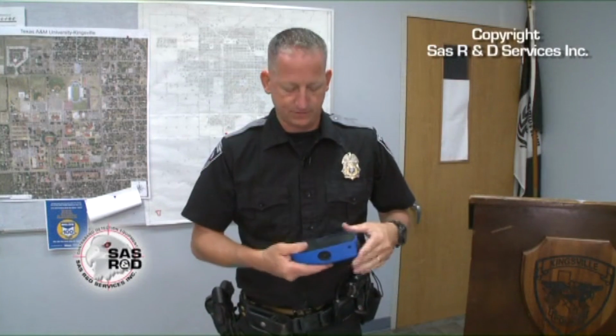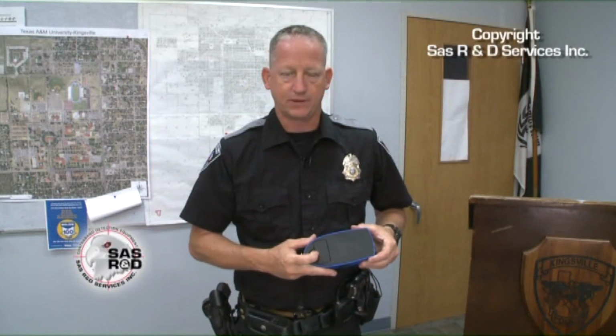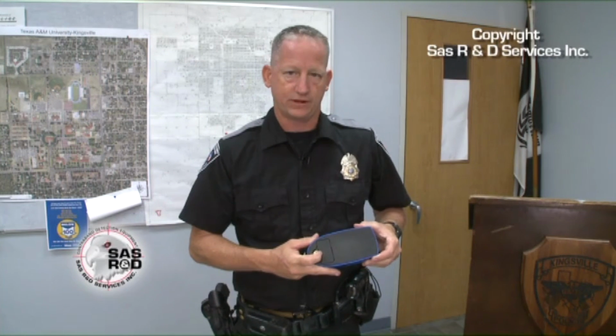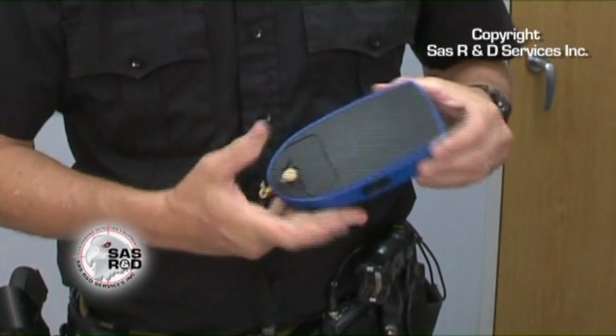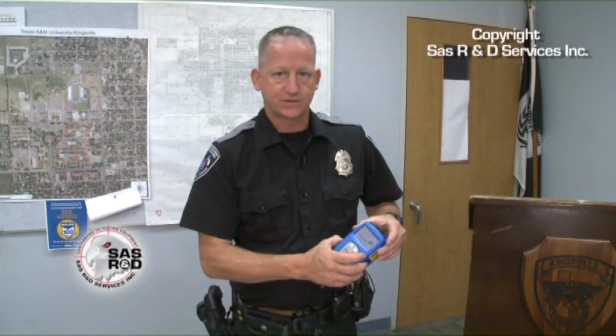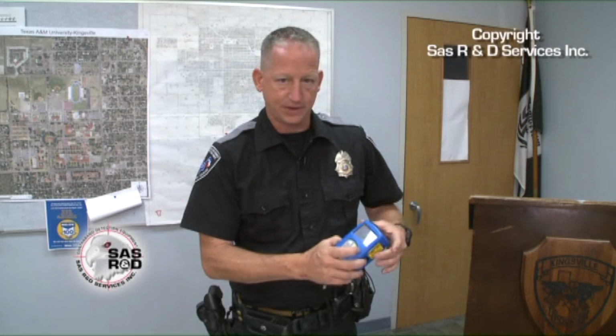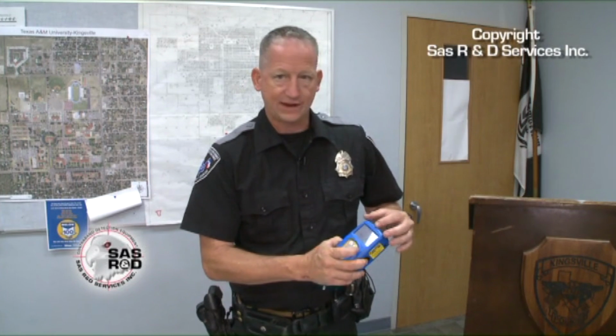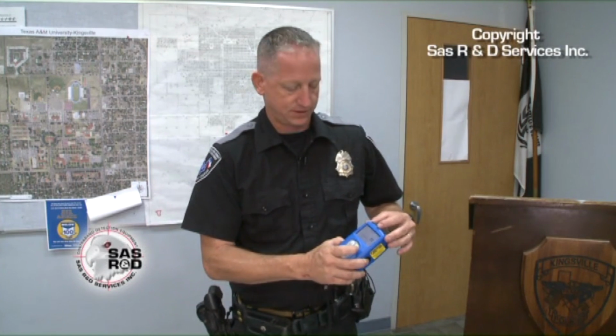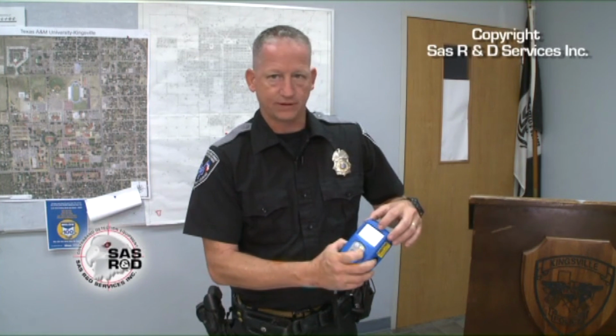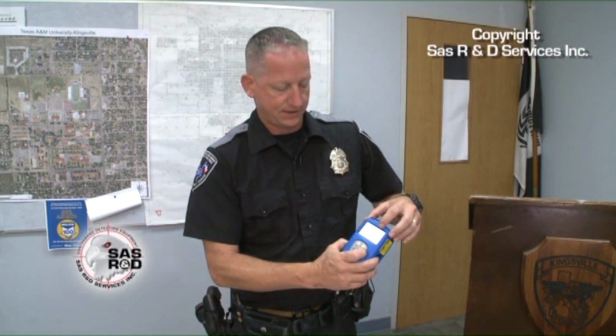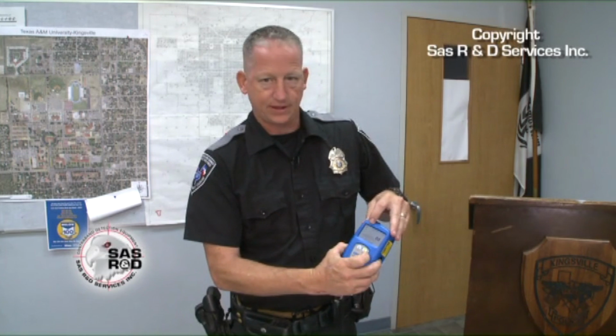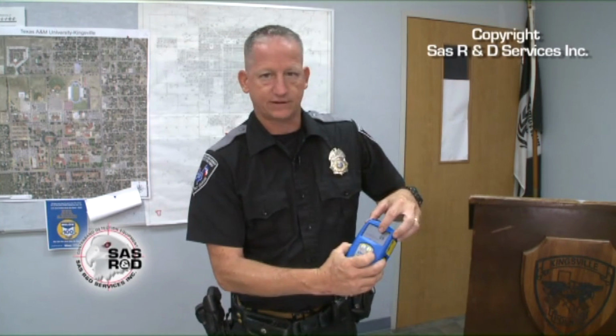This unit is powered by two AA batteries located on the bottom of the detector. By squeezing the two side buttons at the same time, we'll activate the unit and ready it for use. Changes in density will appear on the number dial located in front, as well as a real-time graph with date and time stamp.